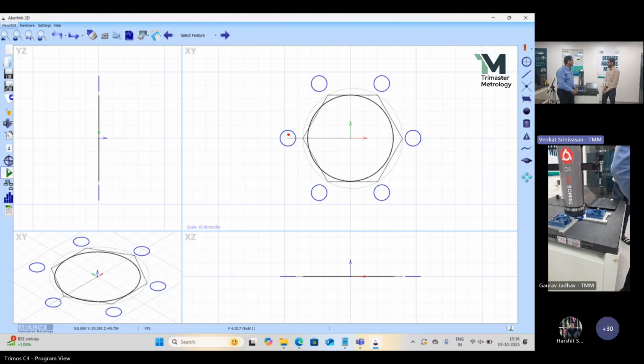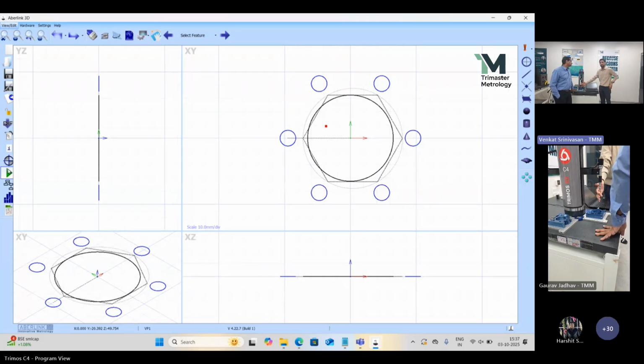Yes, certainly. It's the simplest probing system on the market, a TP20, the TP20 made by Renishaw. This is a touch-trigger-based probing system. It does not offer huge accuracies, but what it does offer is flexibility. Nevertheless, it is well proven for less than 5 microns. Against a scanning probe, there is a bit of compromise here, but what it does offer is it ensures your probes don't get broken as frequently as they do otherwise.